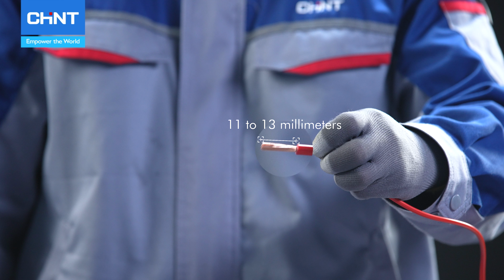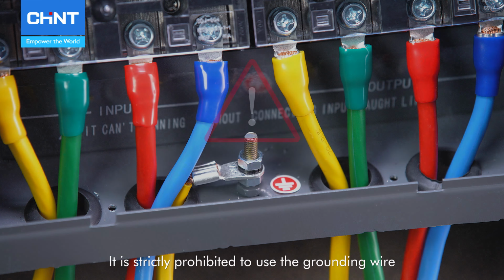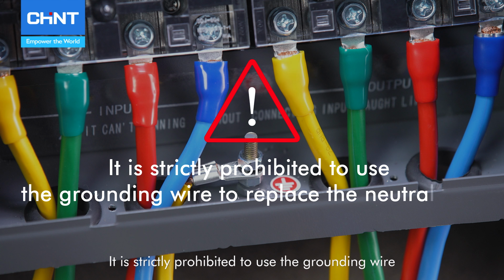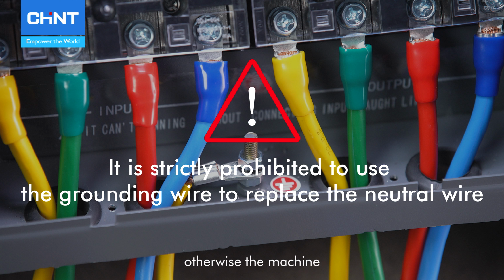Connect the three-phase power supply phase line input and output terminals: L1, L2, L3, N and A, B, C, 0 terminals. The grounding terminal must be grounded to ensure safety. It is strictly prohibited to use the grounding wire to replace the neutral wire, otherwise the machine may get energized or fail to work normally.